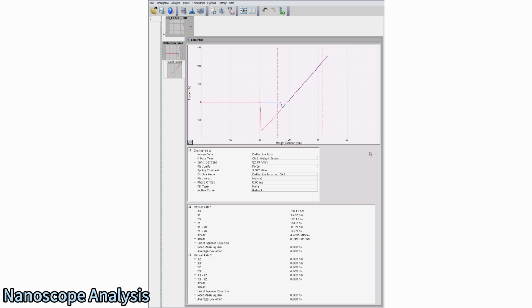To measure the adhesion force, set the active curve to retract, zoom in on the pull-away point if necessary, and move the cursors to either side of the pull-away point. The difference between the y-axis values reflects the adhesion force between the sample and the probe tip. The user has the option of changing the displayed plot units to reflect the force or deflection distance.